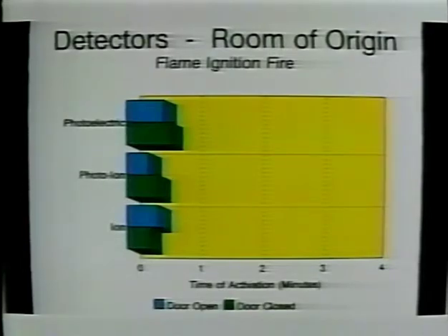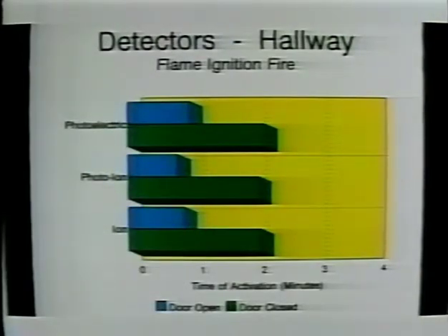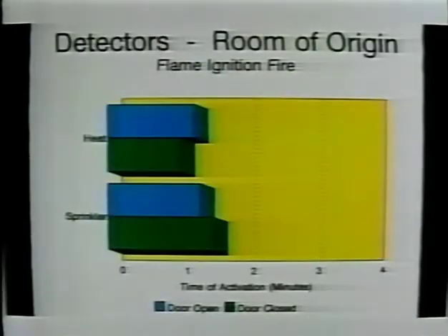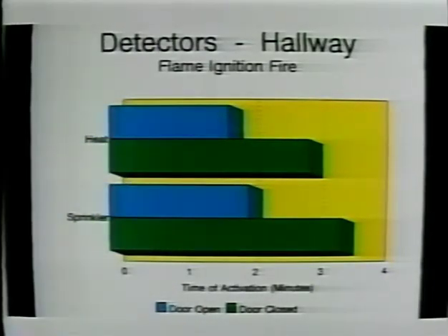All of the smoke detectors in the room of origin activated in less than a minute. The door to the room of origin in a closed position caused over a minute delay in the activation of the smoke detectors in the hallway. The heat detectors in the room of origin activated after approximately 1 minute into the fire. With the door to the room of origin in an open position, the heat detectors activated in less than 2 minutes. The door in a closed position increased the activation time by over a minute.